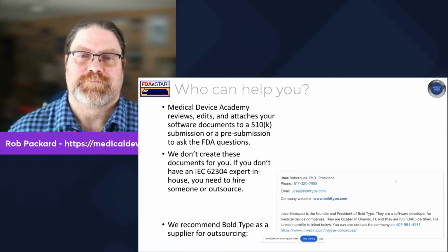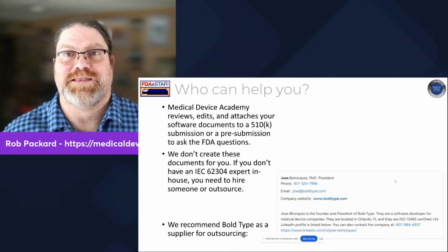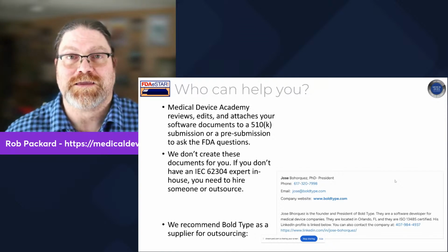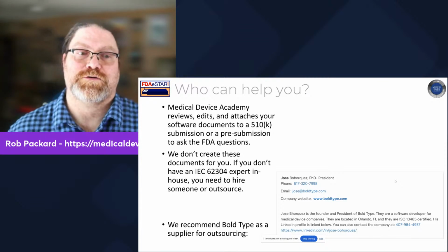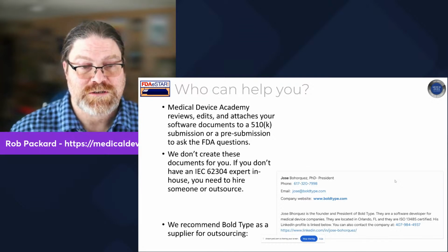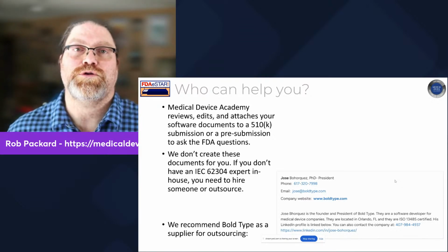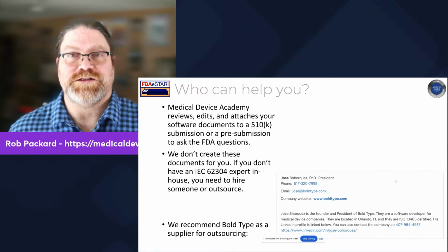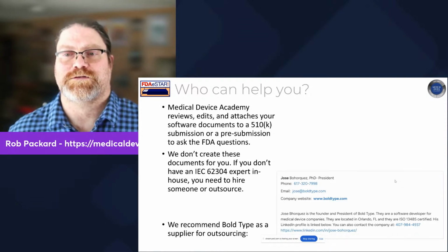But the company's like, but I have software that works. But yeah, I can't validate that because you have nothing documented and you didn't follow the requirements. And you're missing requirements that are regulatory requirements. So start with your foundation, come up with those first 4 documents, hire somebody that's trained. If they don't know 62304, if they don't know those numbers, if that doesn't instantly tell them exactly what kind of project this is, keep looking for a better vendor.